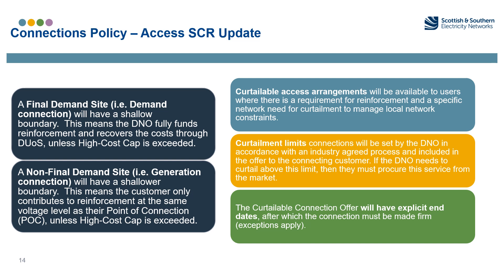Where there is reinforcement identified, the customer can request a curtailable connection. A curtailable access arrangement will be available to users where there is a requirement for reinforcement and a specific network need for curtailment to manage local network constraints. For example, if you are a generation connection and you have triggered reinforcement at the voltage level above, SSEN can offer a curtailable connection to allow you to get connected ahead of the reinforcement being completed, and will provide you with that within an offer.